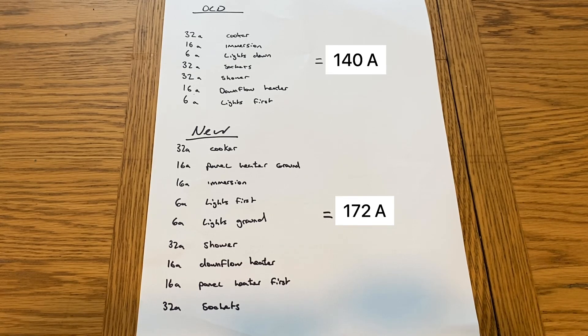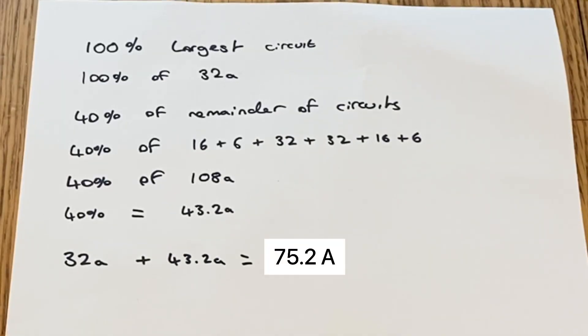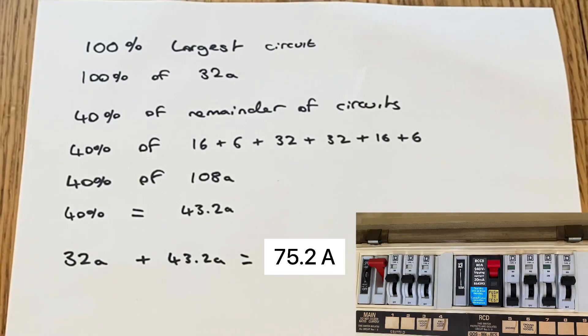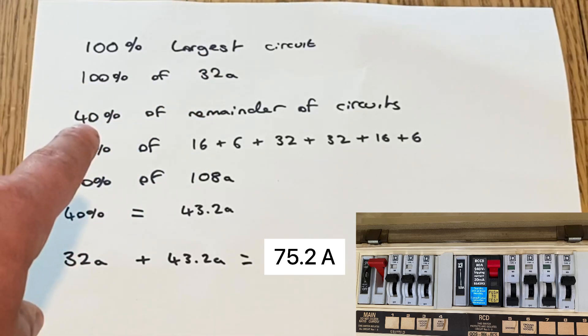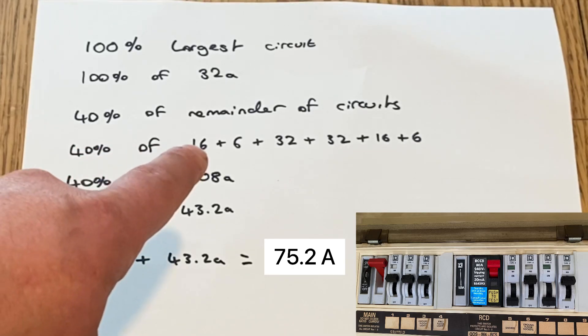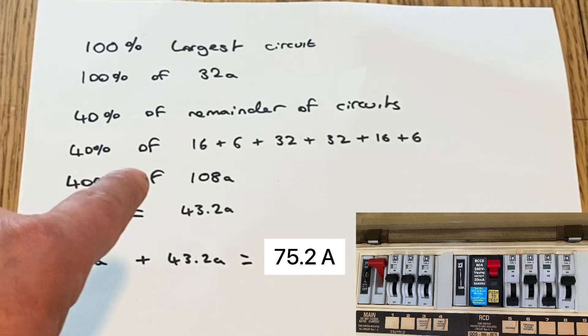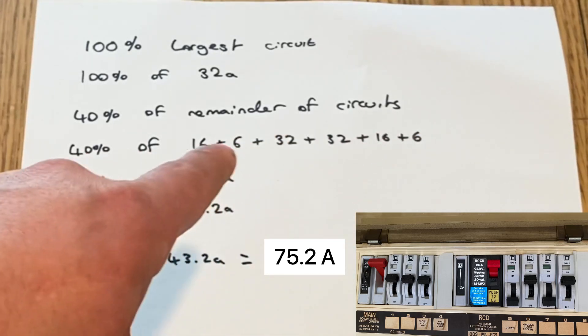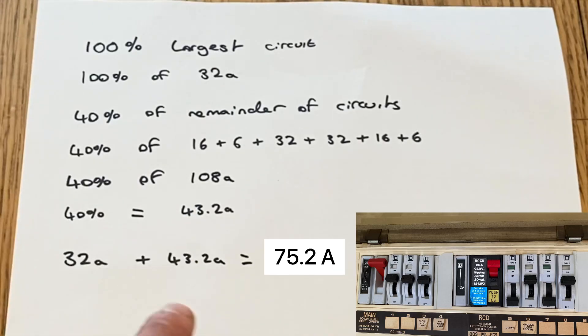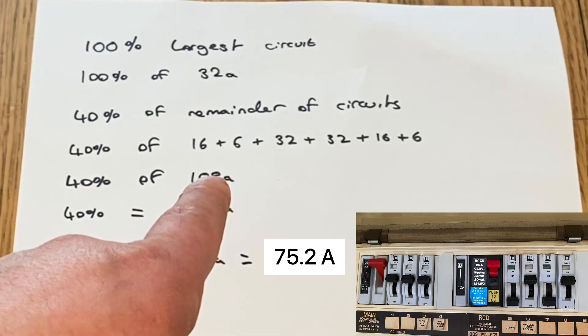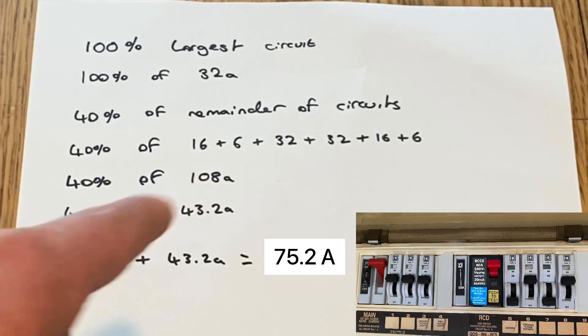As you can see, what we've done first is we took 100% of the largest circuit, which is 32 amps. We've then took 40% of the remainder of the circuits. So 40% of the remainder of the circuits added together, not the 32 amps of the largest that we already took. We would get 108 amps. If we take 40% of 108 amps, the easiest way is if we added our largest circuit of 32 amps to the remainder of our circuits with the diversity included would actually give us 75.2 amps.